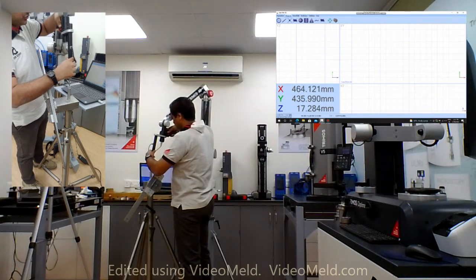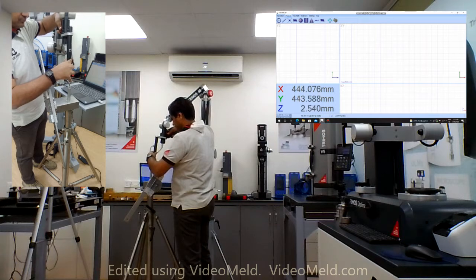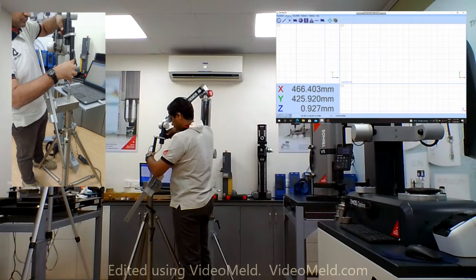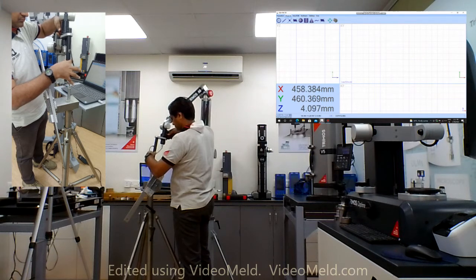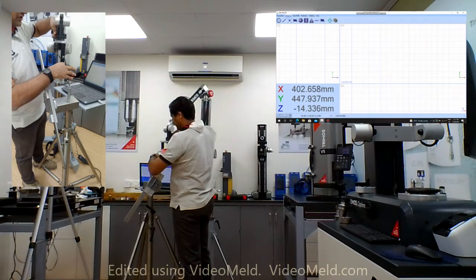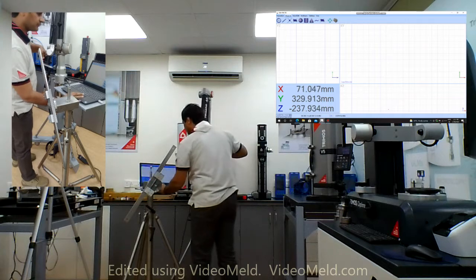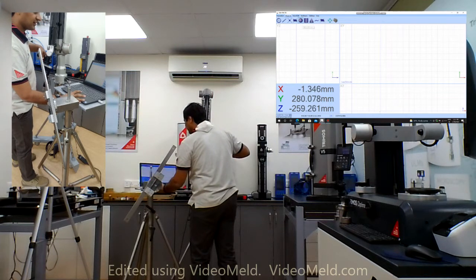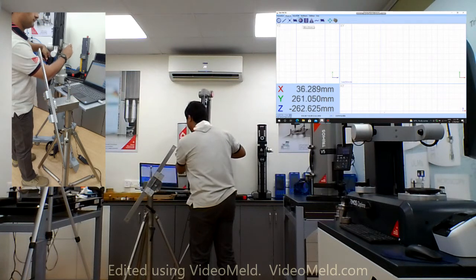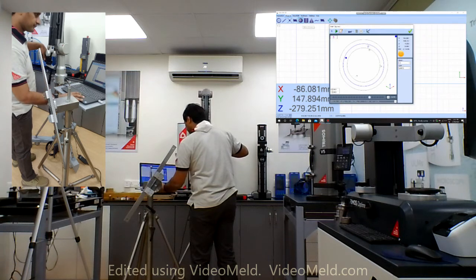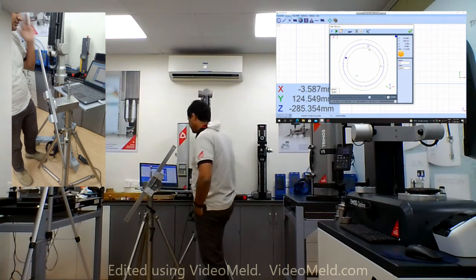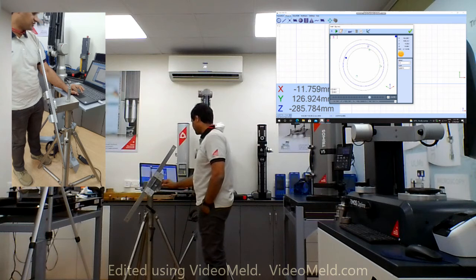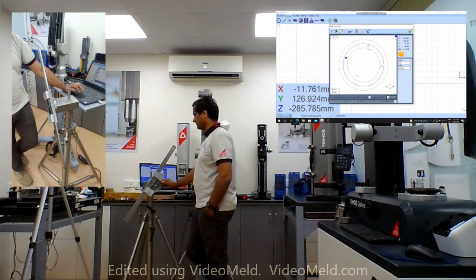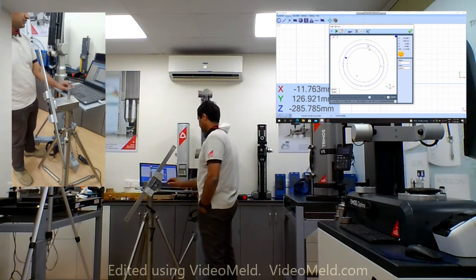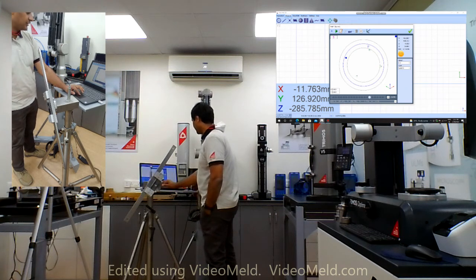You see how easy it is to probe. So I've taken 5 points and selected a sphere. And you can see right here the measured diameter of the sphere is 19.997. This is a 20 millimeter sphere. So extremely good accuracy.